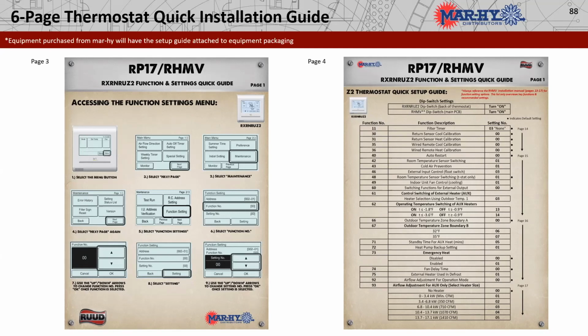We basically have gone through this thermostat and looked at what functions best suit our application for this region. Now, mind you, this is the Northwest, so we did our standard stuff that you might see on a conventional heat pump as far as heat strip switching, those kinds of things. And we've laid it all out for you. As you can see, code 60, setting 60, function 62, setting 13 and 14, those are the different temperature ranges within the thermostat to bring the strip heat on.